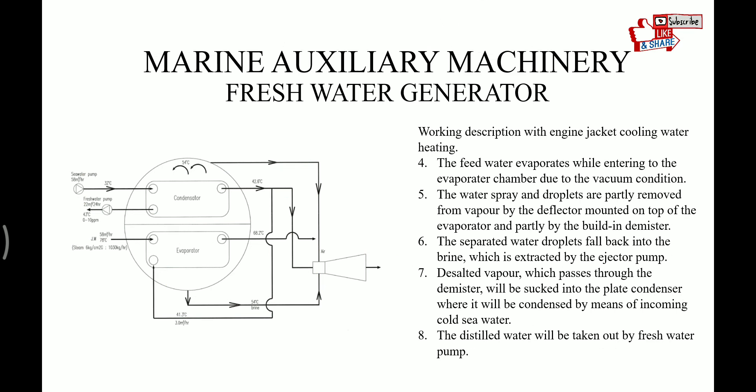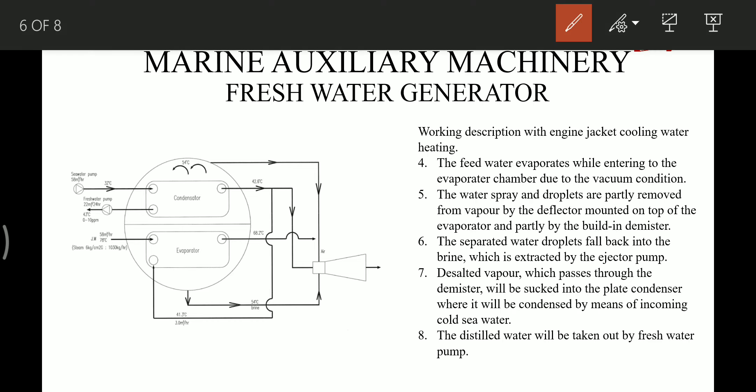The feed water evaporates while entering the evaporator chamber due to vacuum conditions. The water spray and droplets are partially removed from the vapor by a deflector mounted on top of the evaporator and partially by a built-in demister. The demister removes the droplets and salts that evaporate with the steam or vapors. The separated water droplets fall back into the brine, which is extracted by the ejector pump.